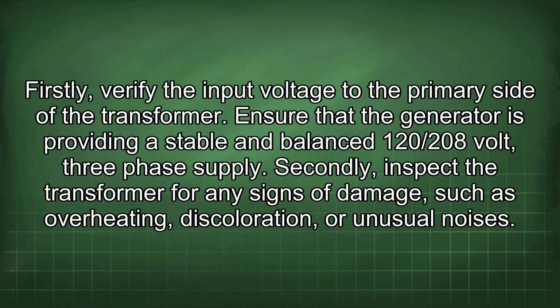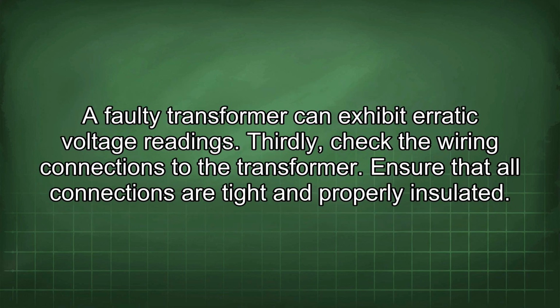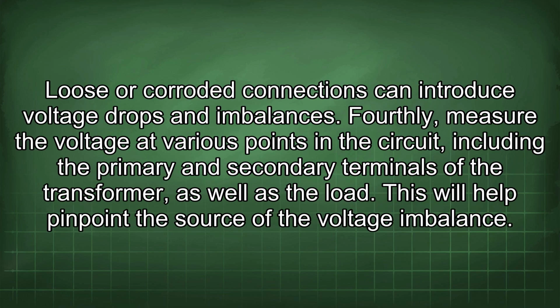Firstly, verify the input voltage to the primary side of the transformer. Ensure that the generator is providing a stable and balanced 120/208 volt 3-phase supply. Secondly, inspect the transformer for any signs of damage, such as overheating, discoloration, or unusual noises. A faulty transformer can exhibit erratic voltage readings. Thirdly, check the wiring connections to the transformer. Ensure that all connections are tight and properly insulated. Loose or corroded connections can introduce voltage drops and imbalances.